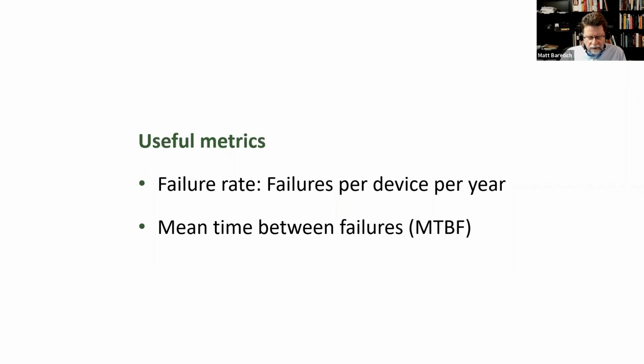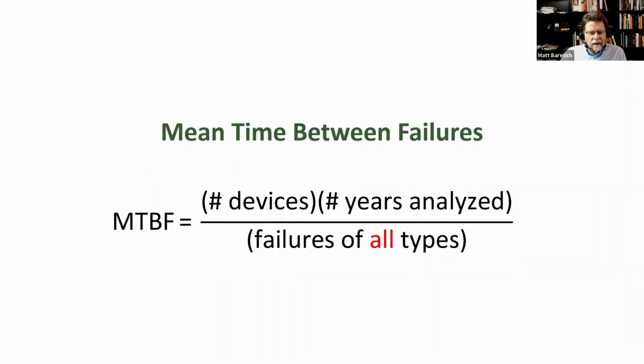Okay, MTBF, next slide. MTBF gets calculated something like this. And it looks at the devices over some period of time and then has a denominator of the failures of all different types and every kind of failure that you can imagine. And that's useful. I would recommend everybody calculates MTBF, but we know that some of these failures are not going to be mitigated by better maintenance, better PM in particular. If the problem is that there's a device that's difficult to program and people tend to misprogram it, then you can PM it all day long and you won't solve that problem. So there's a reason to distinguish PM-related failures from other kinds of failures, and that's where there's some consensus building.